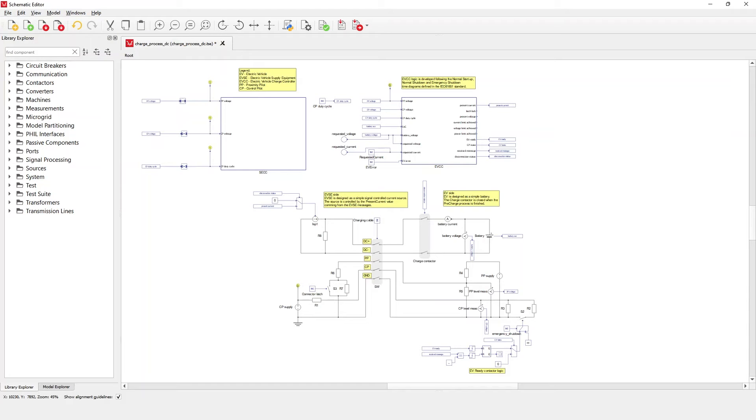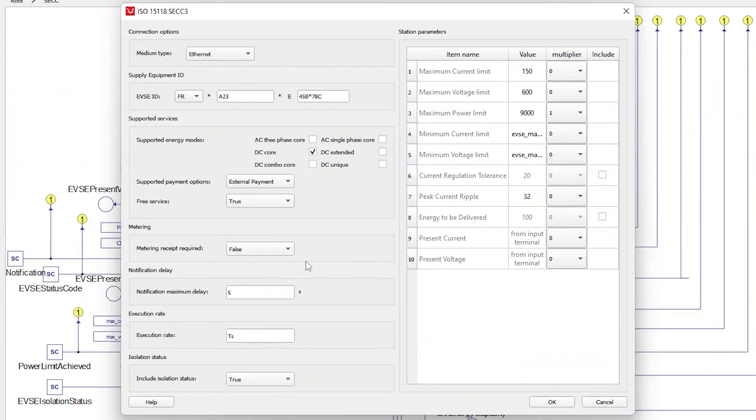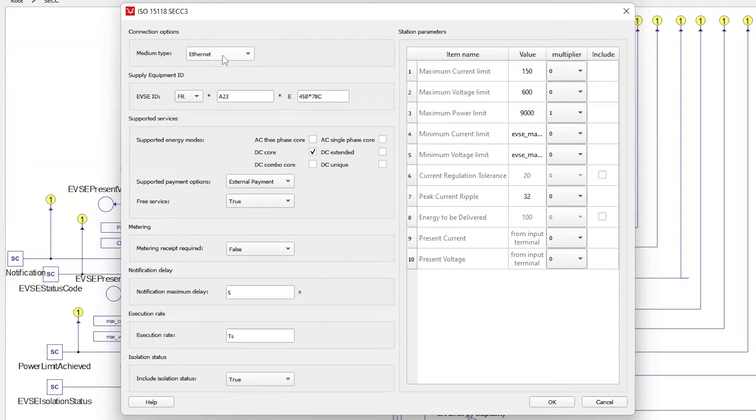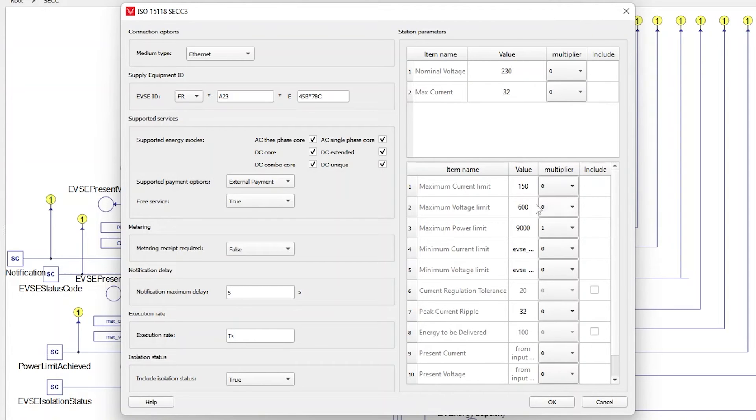Let's start by opening the component properties of the SECC. In the option medium type, it is possible to select Ethernet or power line communication, depending on what physical layer you want to access with the ISO 15118-2 protocol. In the supported energy mode section, it is now possible to select all DC charging modes, as well as combine multiple modes together with AC charging modes, like in a universal charger. Depending on which mode is selected, the station parameters dialog box changes accordingly.